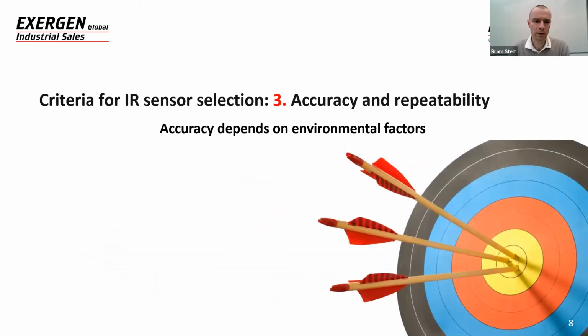Another important criterion for the sensor selection is, of course, accuracy and repeatability. Accuracy is how close a measurement is to the true value. In order to know that, you need to know what the true value is. Repeatability is how well a sensor gives reproducible results under identical circumstances. So it should give consistent readings over and over again. The accuracy is really dependent on environmental factors that can affect it: ambient temperatures, noise from surrounding areas, field of view issues, it can be anything.